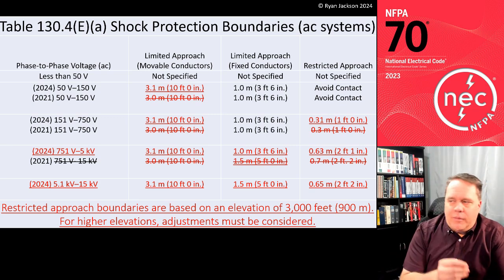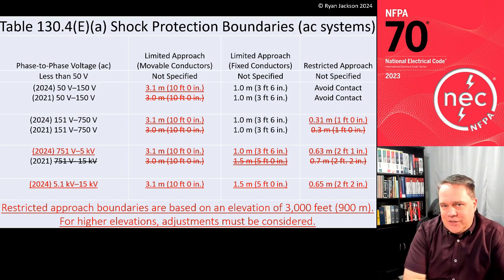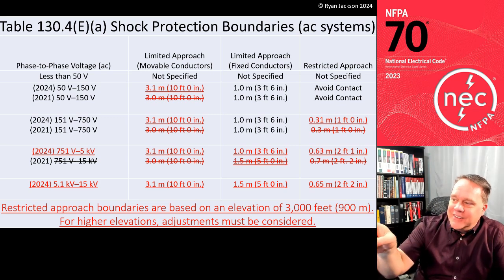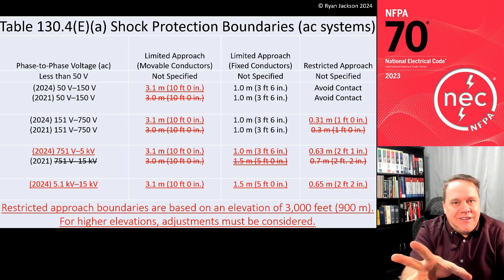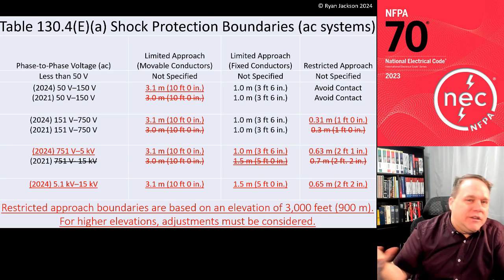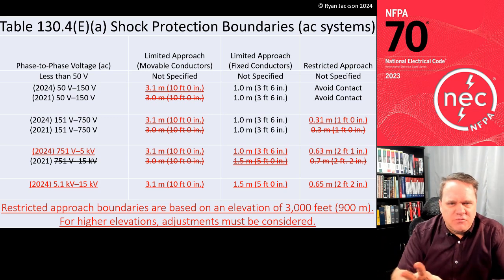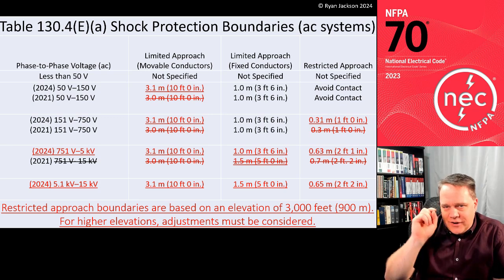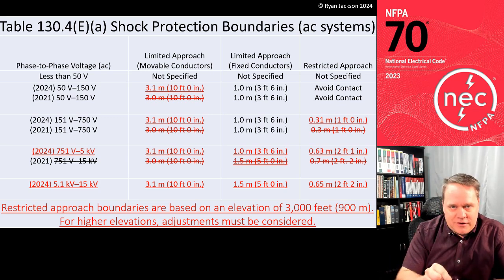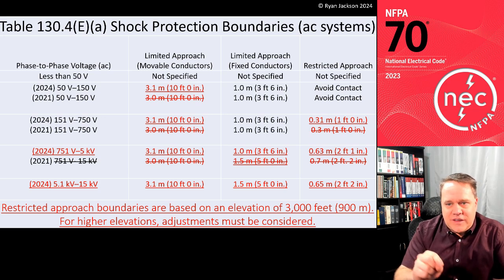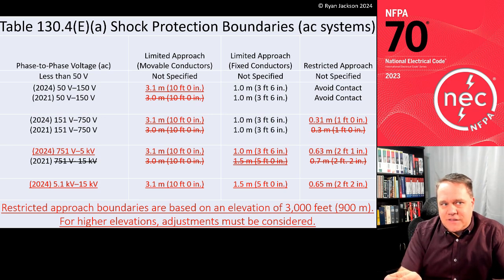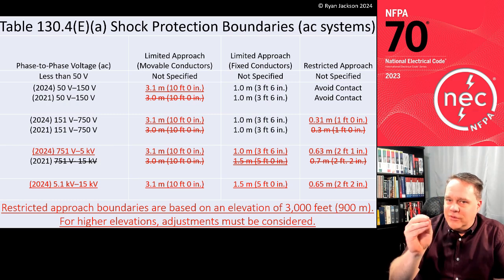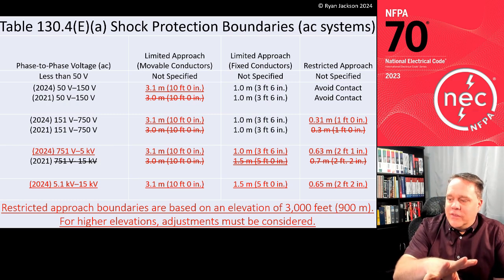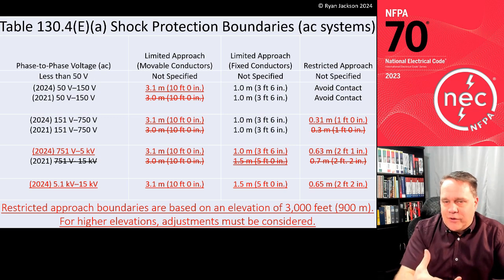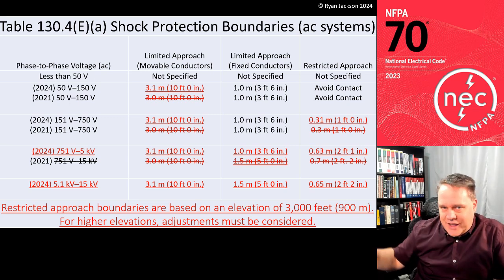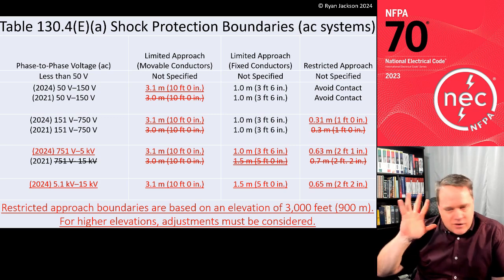But here's the problem. It didn't comply with OSHA. When we made these roundings in the NFPA 70E, we were like, 3 feet, 3 meters, 10 feet, close enough. Well, OSHA says 3 meters. So when we say 10 feet, that's not 3 meters. So when we rounded them, we didn't round them conservatively. We rounded them in the way of not establishing safety. So I know this is dumb.